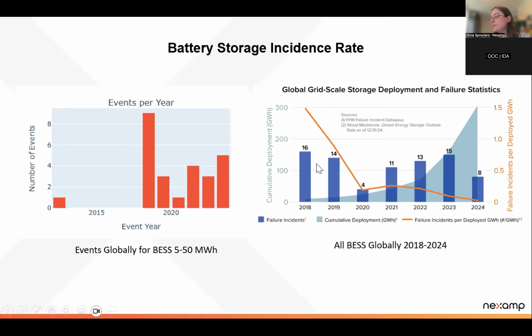As you can see, in 2018, 2019, and 2020 there were a number of incidents, but these were generally with types of technologies no longer employed today. A lot of these are nickel manganese cobalt batteries, which tend to burst into flames when they overheat, rather than have a gradual off-gassing event that just requires observation. They're also a lot less stable and need to be more strictly maintained for there not to be an emergency event.